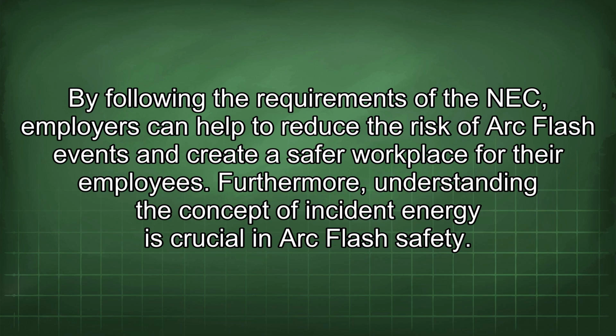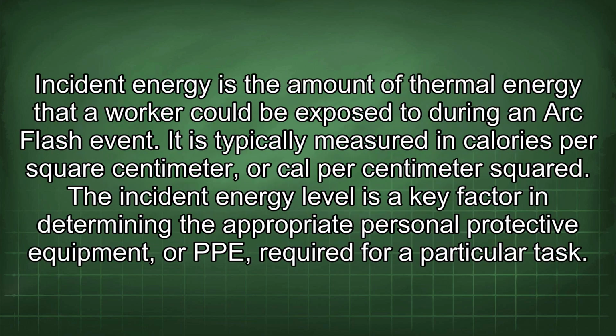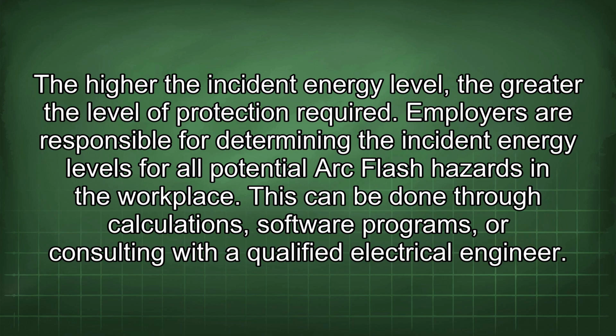Furthermore, understanding the concept of incident energy is crucial in arc flash safety. Incident energy is the amount of thermal energy that a worker could be exposed to during an arc flash event. It is typically measured in calories per square centimeter, or cal per centimeter squared. The incident energy level is a key factor in determining the appropriate personal protective equipment, or PPE, required for a particular task. The higher the incident energy level, the greater the level of protection required.